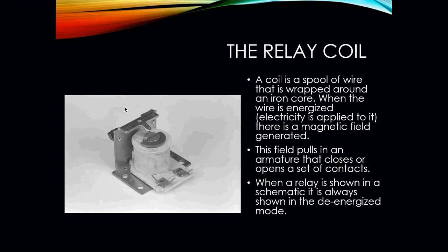Well, we need to have a relay coil. The relay coil is a spool of wire that is wrapped around an iron core. And when we energize that wire with electricity, we generate a magnetic field. So here is my coil of wire right there. My power that would be energizing this coil is connected right here. And right here is that iron core that we were mentioning, right there in the center. So when I energize this coil, I generate a magnetic field. And then that magnetic field pulls an armature, which will then close or open a set of contacts.